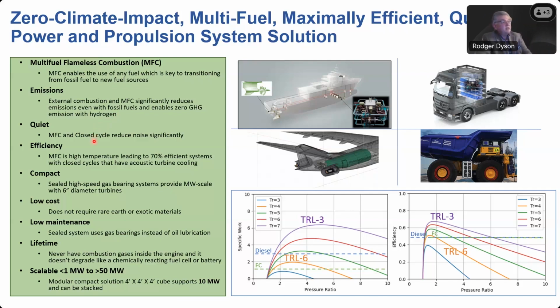It's quiet because it's a closed cycle. All you have is an external combustion heat source, so all you hear is combustion. It's very efficient, as I'm showing in these charts. It's very compact. This is a megawatt scale - a 10 megawatt system is about 4 feet by 4 feet by 4 feet cube. I'll show that a little later.